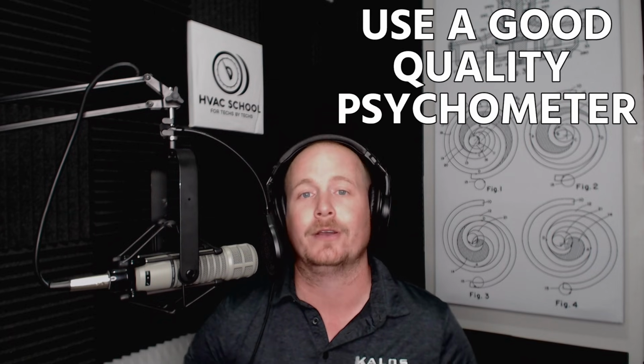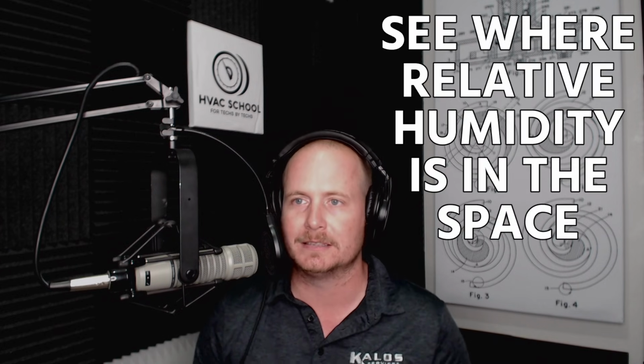And then also UEI makes it as part of their Hub 6 kit, as part of their Hub kit. They also make some really nice psychrometers that you can use. But regardless, in order to see what dew point is in a space, you have to use a good quality psychrometer. You have to let it acclimate to the space humidity. And that's one of the really big starting points. Before you start diagnosing and figuring out exactly what to do, first see where your relative humidity is in the space. And then you can look at things like maybe your vent surface temperature.